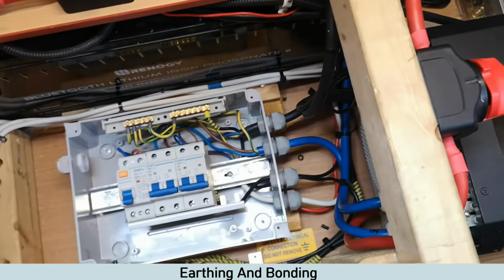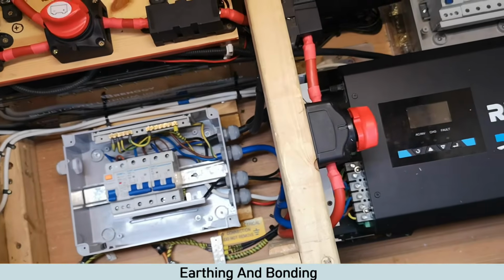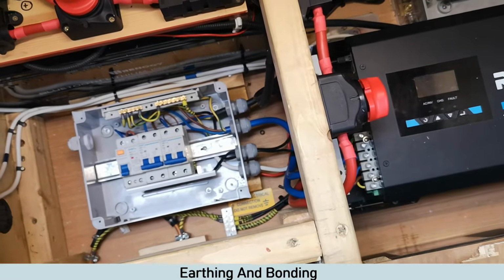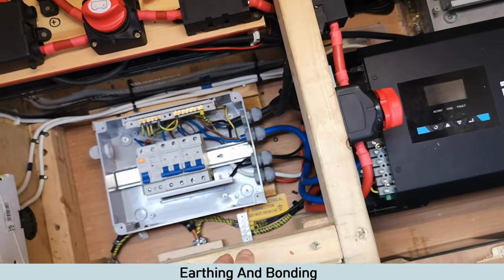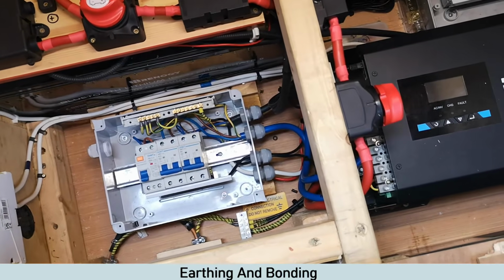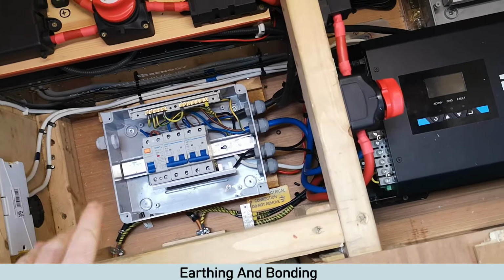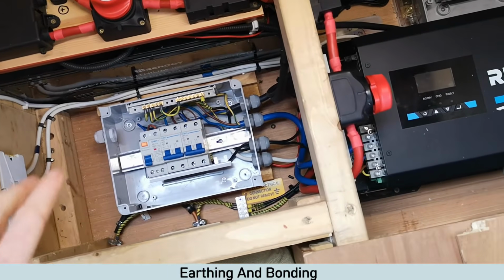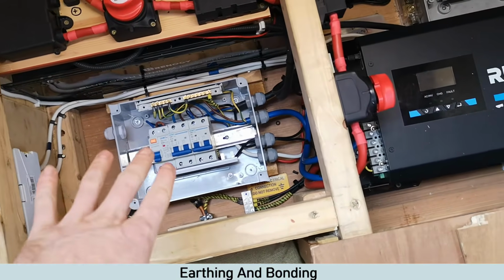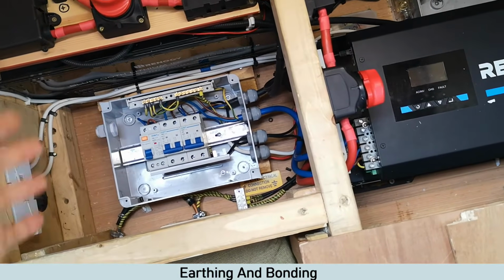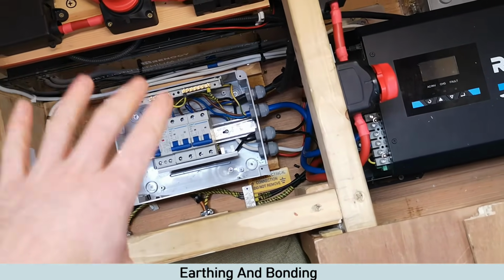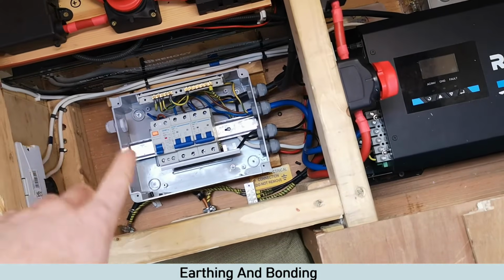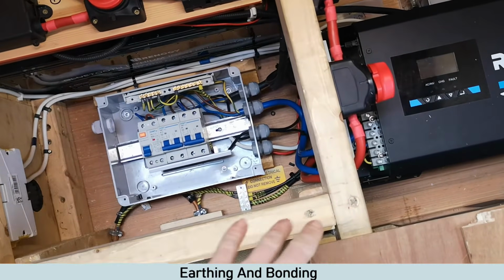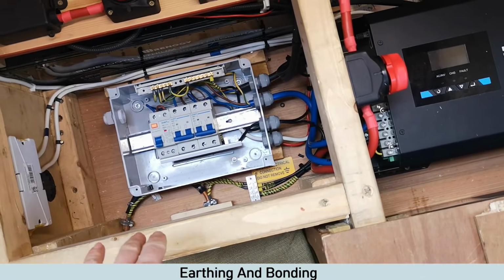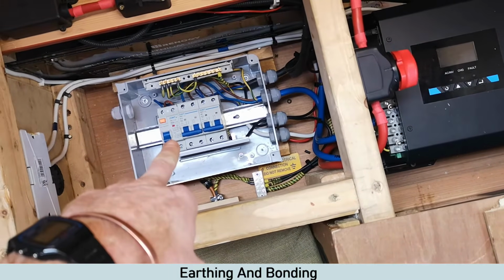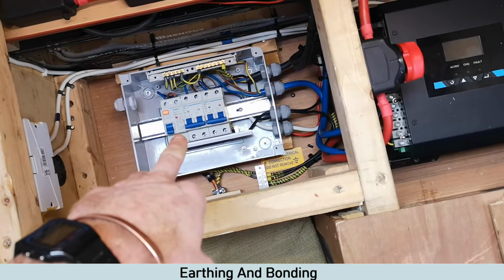So that then is our bonding setup. We've been asked a lot, and there's a lot of confusion in regards to do you bond the chassis, do you bond pipe work, things like that. For us, in our installation, for safety, yes, everything is bonded. So for that reason, if there's ever a fault in the cable or anything, in regards to electric hookup with an RCD, it creates a fault path. So if there's a fault to an earth anywhere, it's actually got a path to trace back through, which will ensure that this RCD will trip out.